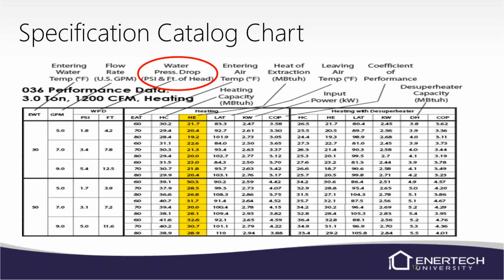So water pressure drop in feet of head, we don't really use feet of head. That's more for sizing of a pump. So if you need to size a pump for a 4,000 foot loop field for this amount of feet of head, then you can also add in your feet of head for the unit as well to make sure that your pumping is where it should be. Your pump will be big enough to flow through properly through the system.